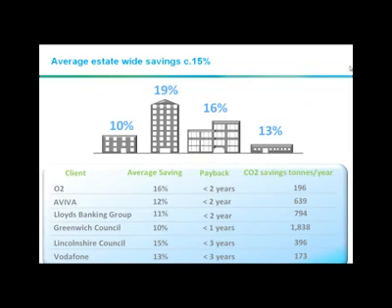Here is, if you like, some UK examples. Clearly across any building estate, you have all different buildings of all different profiles and building fabrics. It's not a uniform saving that you will get across. All the variables, as you can see, are involved. But clearly reducing the times that the boilers don't need to fire will save fuel and put less stress on the boilers. Clearly the most efficient boiler is the one that's not firing.